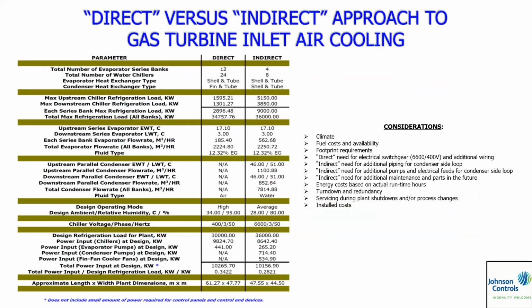All right, so here's a comparison. The direct approach: 24 chillers. Remember that, all those chillers? 24 of them versus 8 centrifugals. Remember the different heat exchanger types. Both evaporators are shell and tube, but the difference on the condensers was that in the direct approach they were air-cooled condensers. On the indirect, they were water-cooled shell and tube heat exchangers.